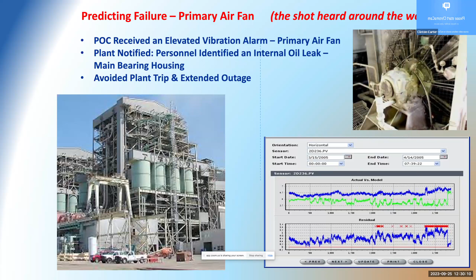we'll go look. And what they found was one of their big air fans that provides forced air input into their boiler. They found a massive oil leak on the main drive bearing, and the draft of the fan had drawn the oil out of the bearing, and it was in catastrophic failure mode. So they were able to take that machine offline without tripping the unit and repair and get it back. So we literally saved a power plant trip and a catastrophic failure on day one.